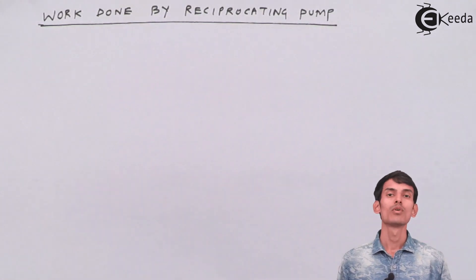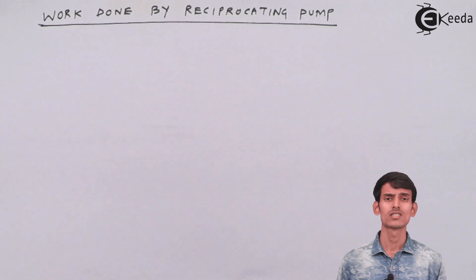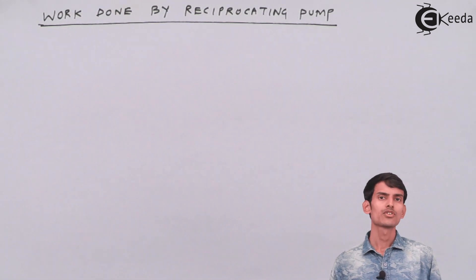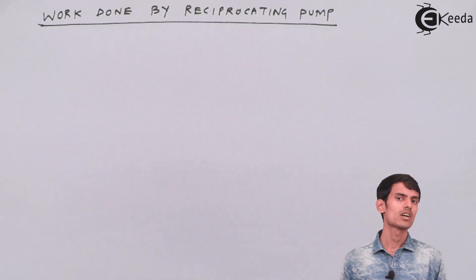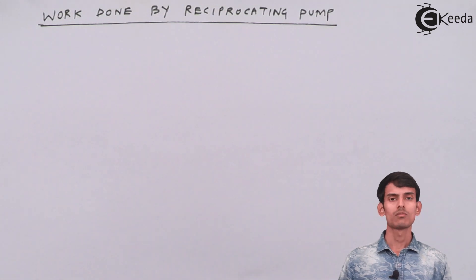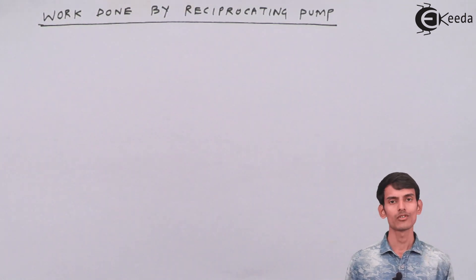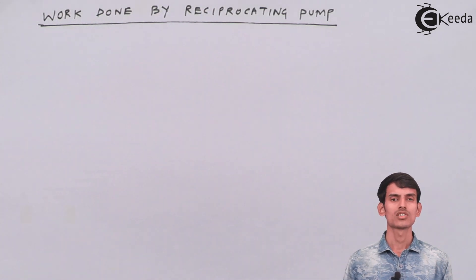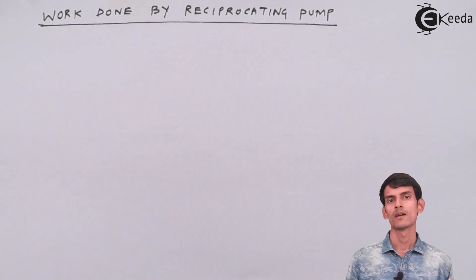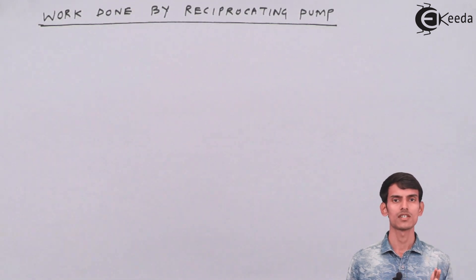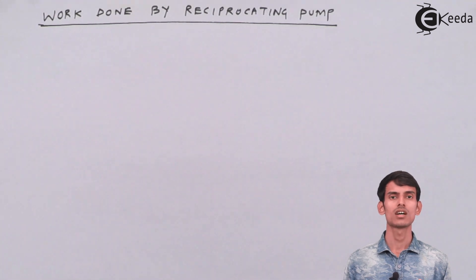The topic of work done by reciprocating pumps is a pretty simple one. For that, you should know how much water is getting discharged every stroke. The volume of water discharged is nothing but the cross-sectional area of the piston into the length through which it is displacing — we call it the swept volume. That is the amount of volume getting discharged in one stroke.